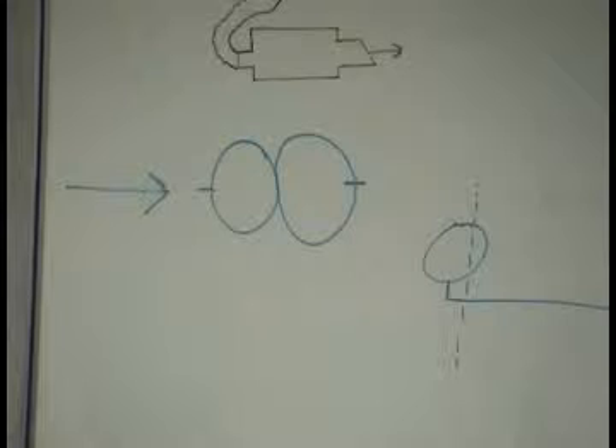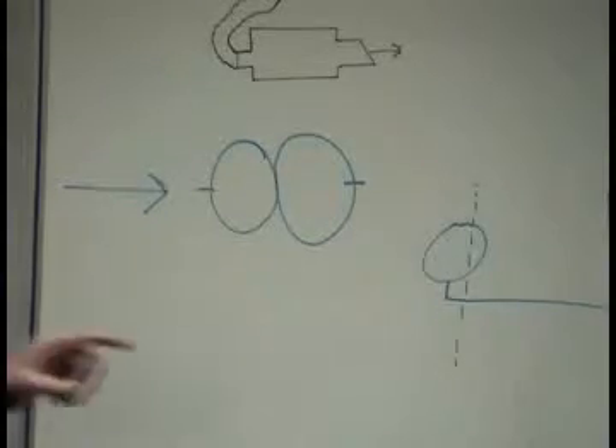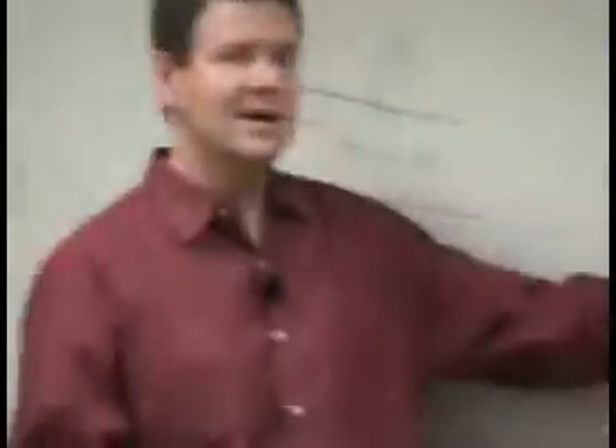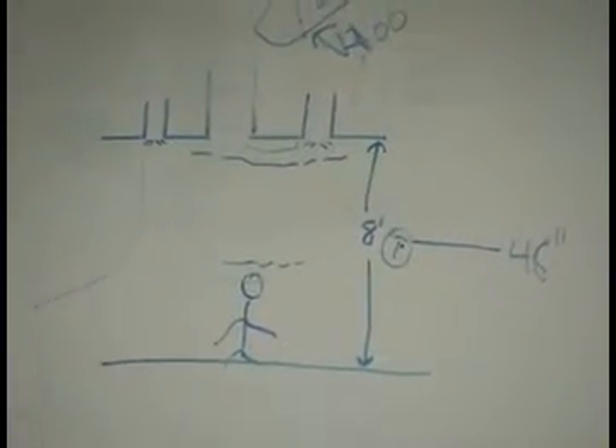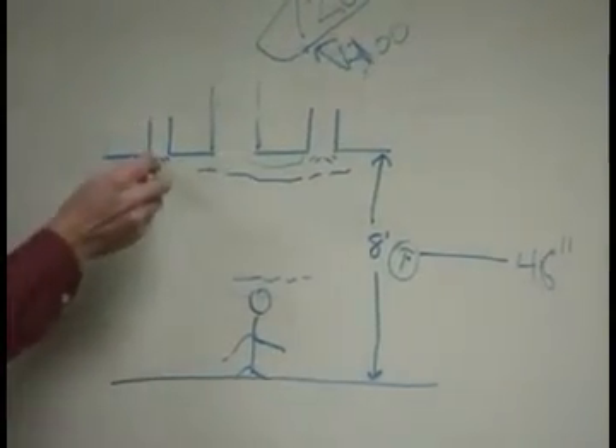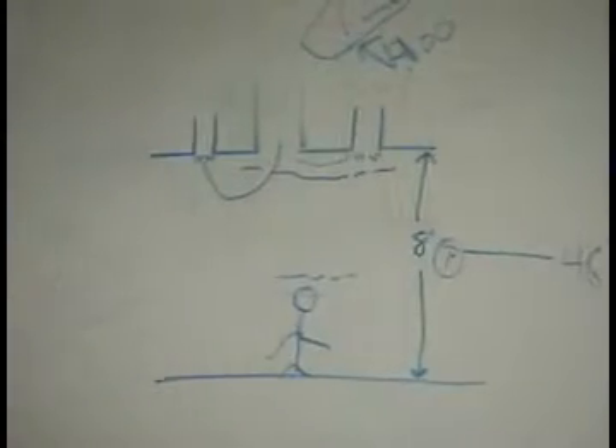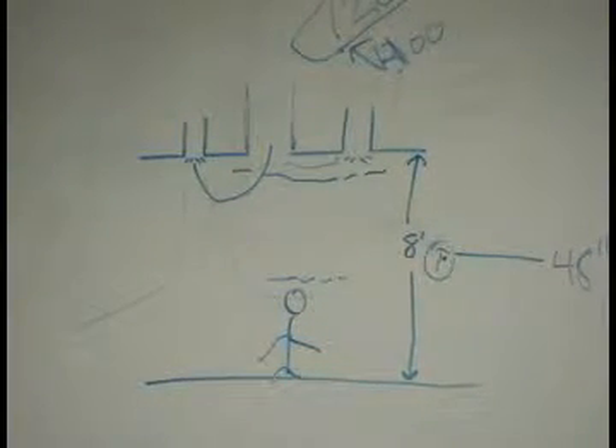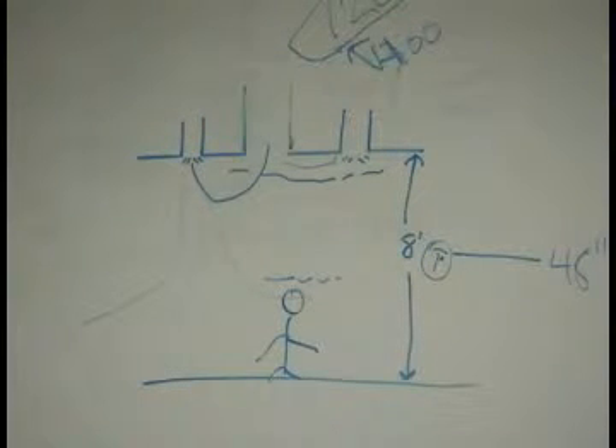The greater the temperature difference between the two streams of air, the harder it is going to be to mix them. The problem with this situation ever working is it's like rolling uphill. Every time you roll it up, it wants to roll right back. The fan is pulling the air up, and you're trying to push the air down, and it's going to want to come back up. So natural flow is going to be back up to the register, to the return grill.